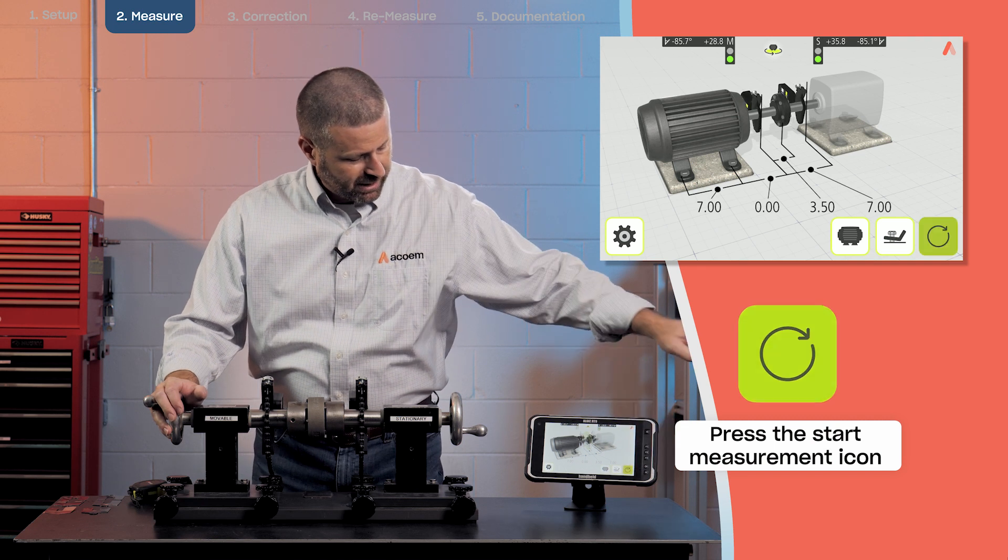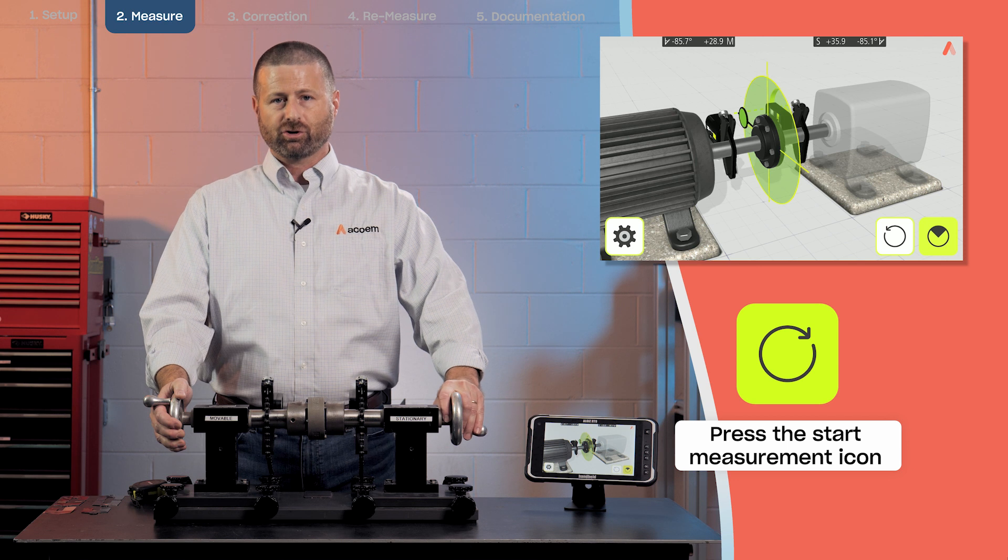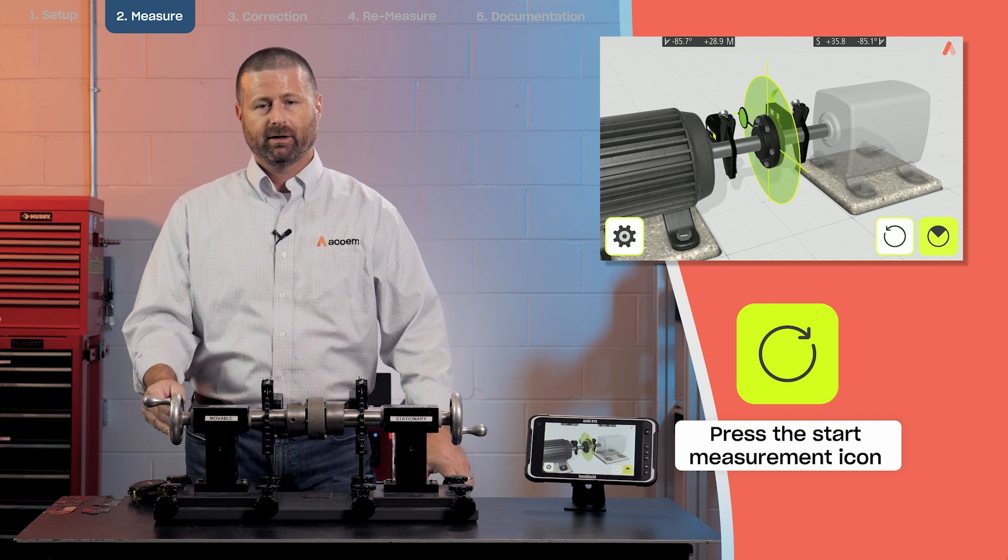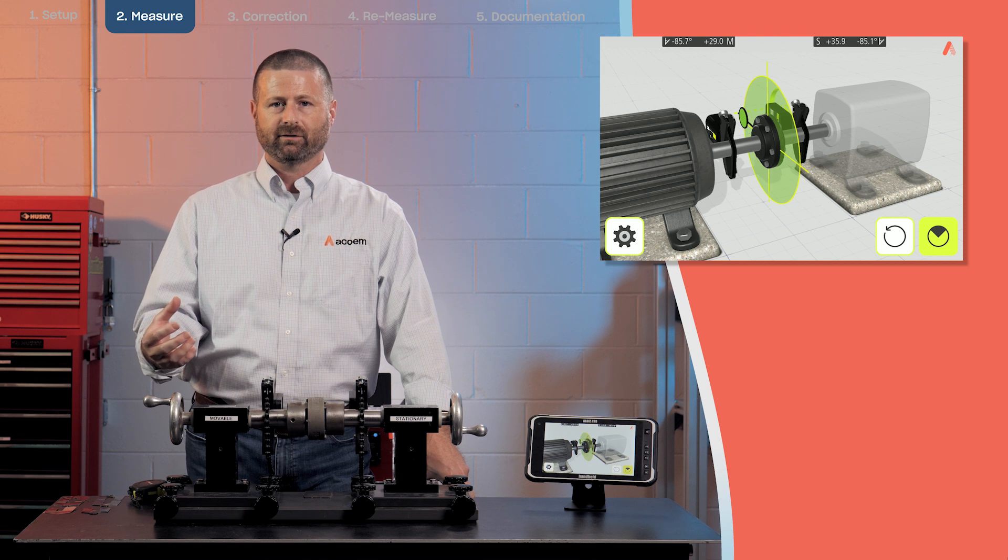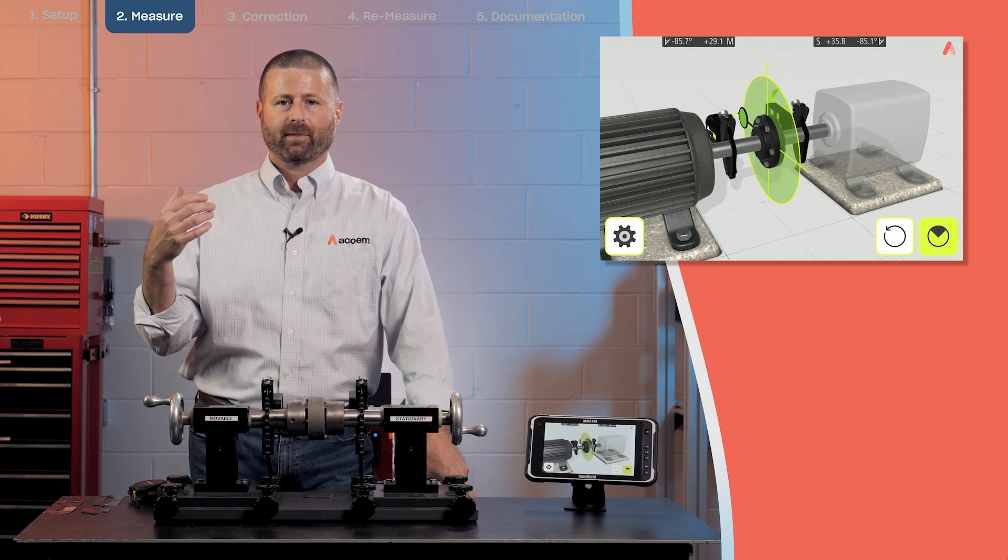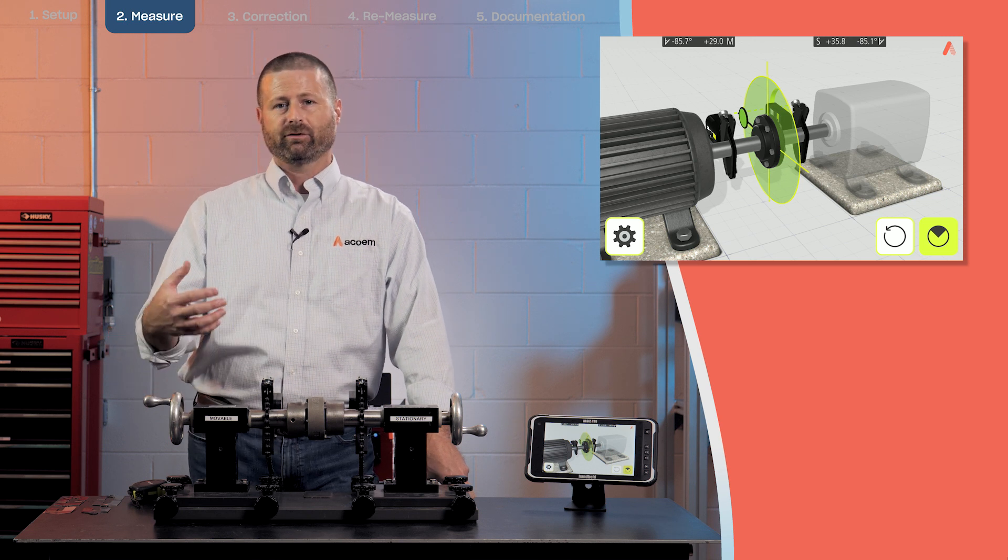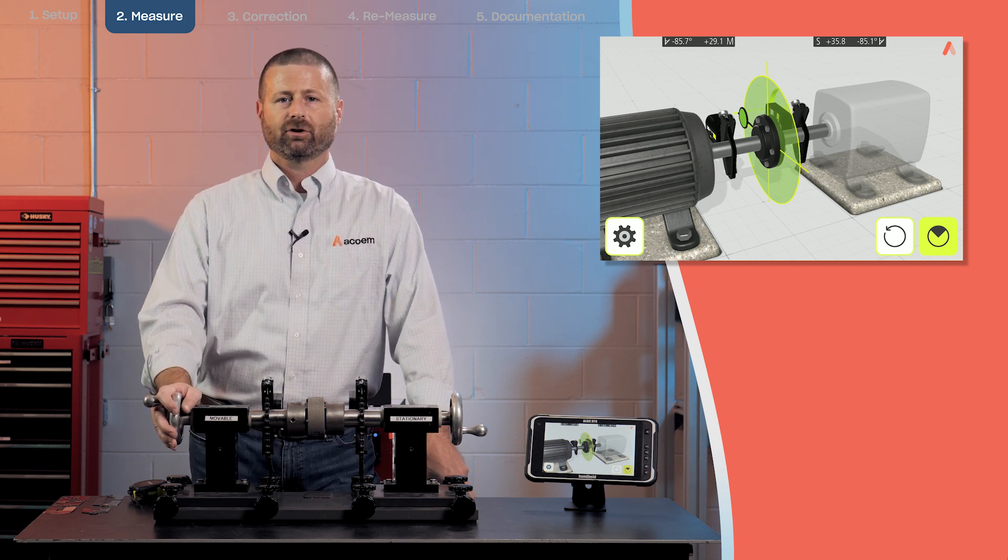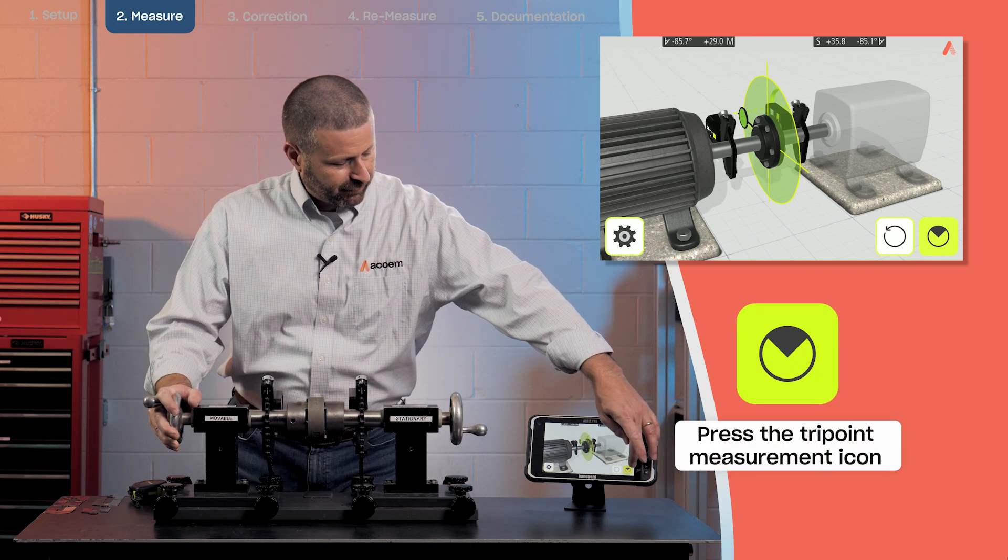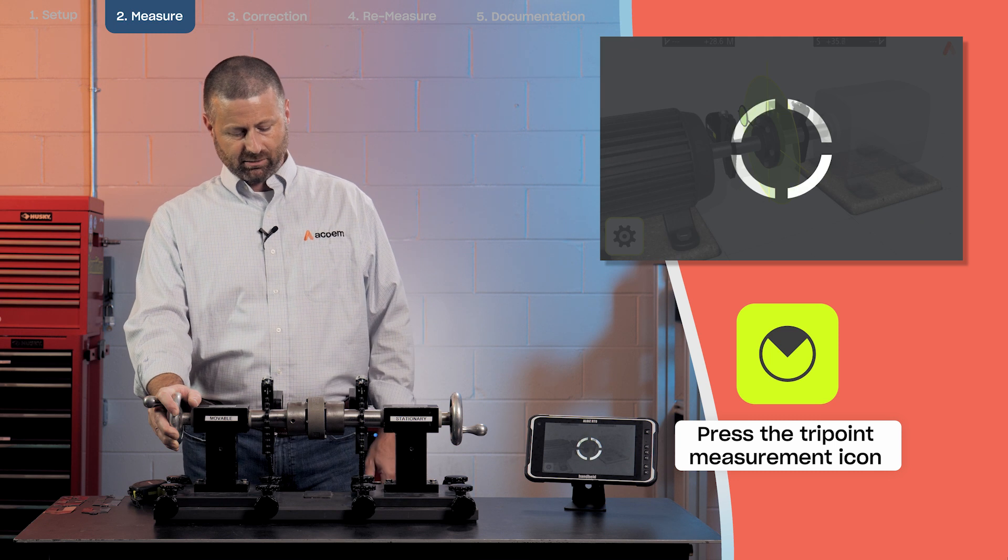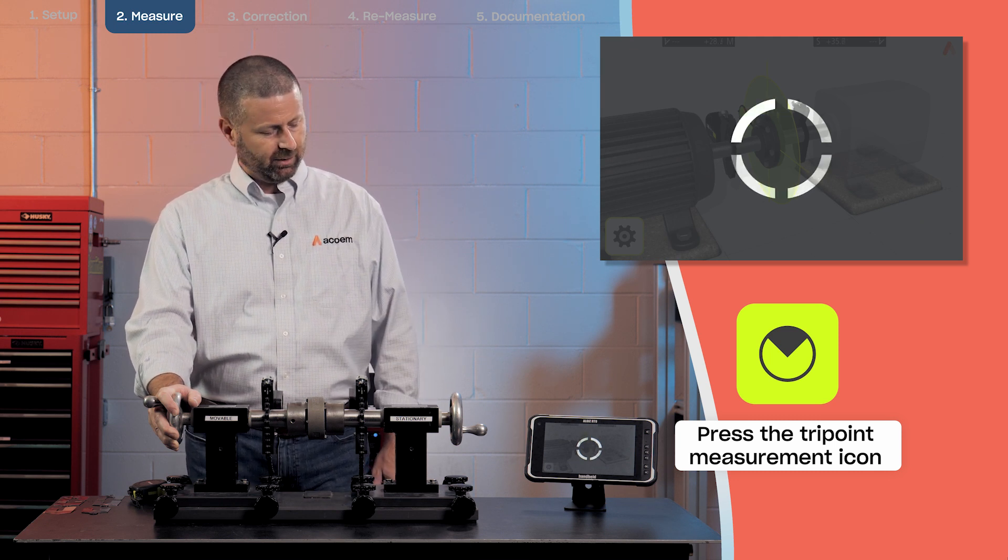I will hit the measurement icon and in AT100 we use our tri-point measurement method. In tri-point it requires us to take three measurements and the measurements can start anywhere and stop anywhere. In other words there's no requirement to use clock positions in tri-point. So I'll take my first measurement at this location which is somewhere between nine o'clock and 12 o'clock.